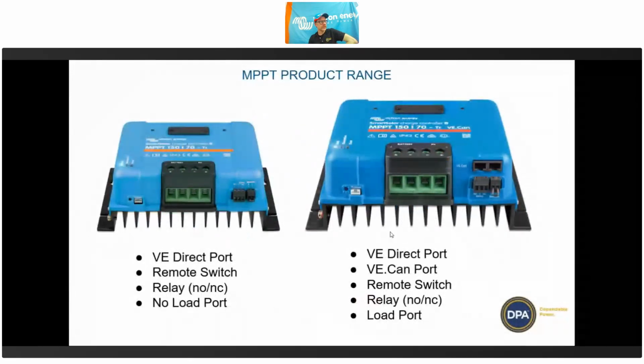And then as you go up the range, there's some more features added. So these larger ones here, the 150, starting with the 150/70, they also have a relay built into them, a programmable relay. And then they also have a remote. So the remote is just a way of turning this off and on with a switch. You can't really see it very well, but on the right-hand side here, you can see it well. It's just a little jumper, goes from one side to the other side. So if you pull that out, it will stop working because it needs to connect one side to the other side to operate. So what you can do is you can take that little jumper out and you can wire that with a bit of twin cable to a switch that you have somewhere else.